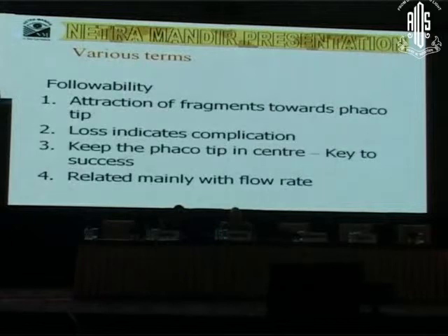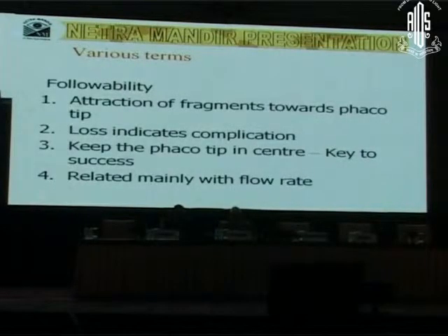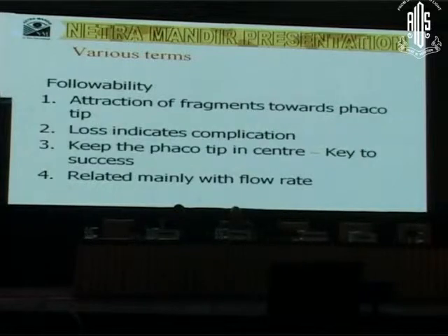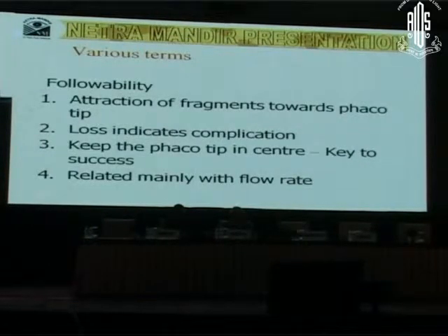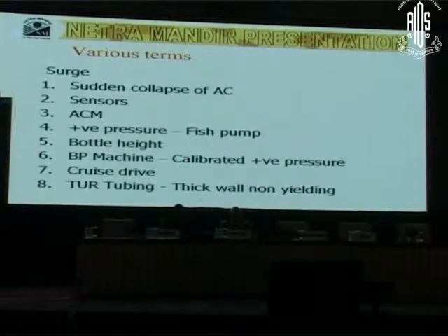Followability, I think, is one of the most important things you need to remember while you are doing phacoemulsification, which attracts the nuclear pieces towards the phaco tip. Loss of followability implies that there is some complication, and at that point, you need to review your case very well after injecting viscoelastic material and be sure that you have not ended up in any complication.